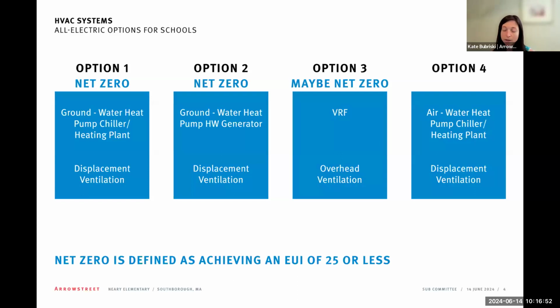To really determine whether it could be net zero would rely on every unique building and doing an energy model of that building. And then option 4 is an air to water heat pump chiller heating plant. Essentially, that is using a heat pump chiller to produce chilled water, and it also has a supplemental electric boiler. So this is the least efficient of all these systems. It's in the high 20s to 30 EUI. It's not a net zero system, but it is potentially more traditional for people who might be used to a boiler chiller kind of situation in a building. This is just an electric boiler instead of gas.